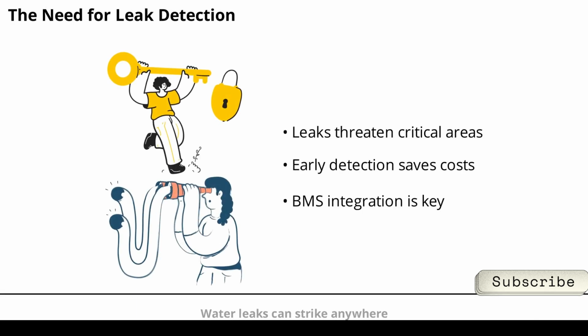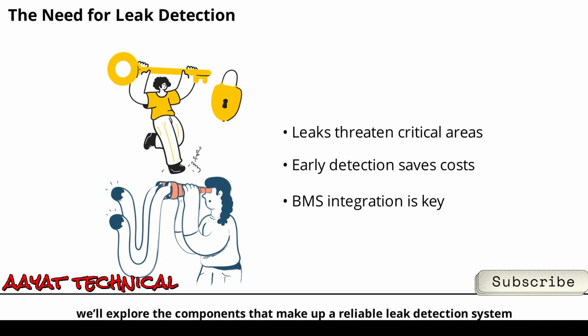Water leaks can strike anywhere, but they're especially dangerous in critical areas like data centers, electrical rooms, and under raised floors. Even a small leak can cause major equipment damage, downtime, and safety hazards. That's why leak detection is a must-have in modern buildings. By integrating leak detection with BMS, facility teams can spot problems early, respond quickly, and prevent costly disasters. Next, we'll explore the components that make up a reliable leak detection system.